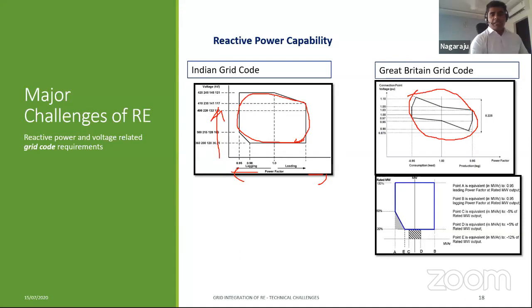So that is the reactive power related challenge. Here I'm only talking about the static reactive power capability, but when it comes to the dynamic reactive power, the generators have to have reactive power support in this entire range as a function of time as well. When the grid asks to provide reactive power, from the time it gives a signal to a generator, the reactive power support should be available within 1 second, at least as far as I know in UK. Within 1 second, the turbine or solar farm has to move from fully lagging to fully leading and vice versa. So that kind of dynamic response is also required, not just the static requirement. That's what makes them challenging.